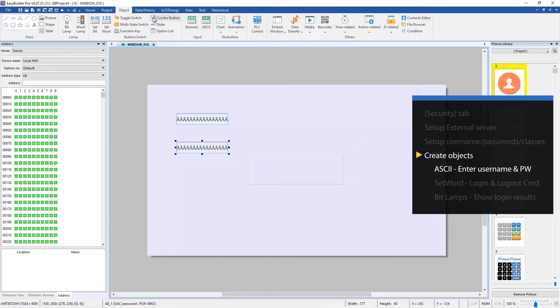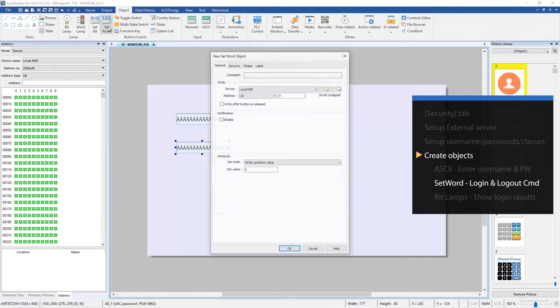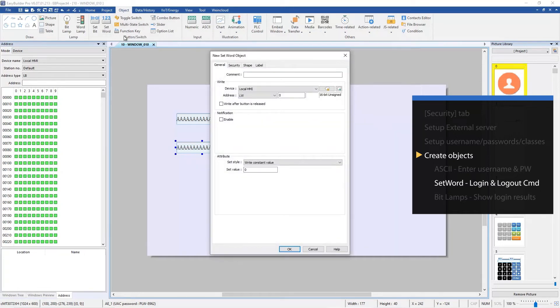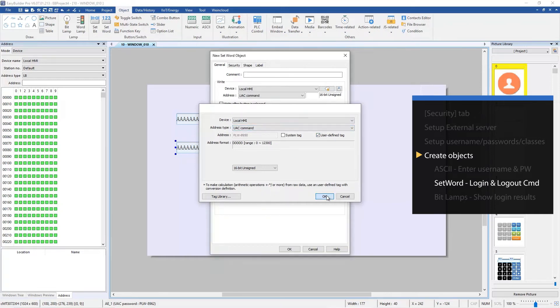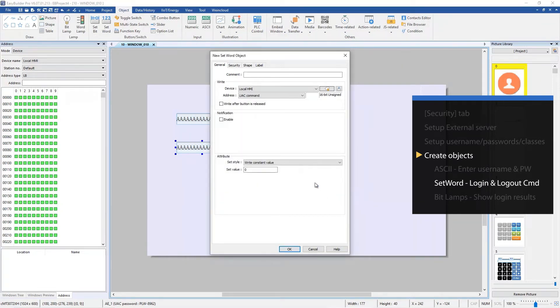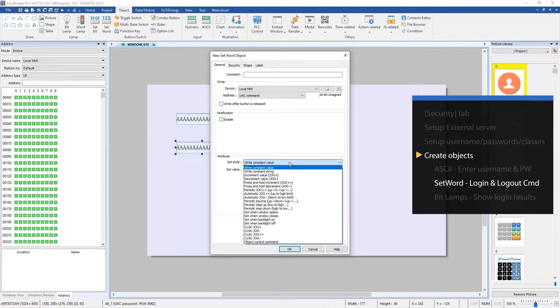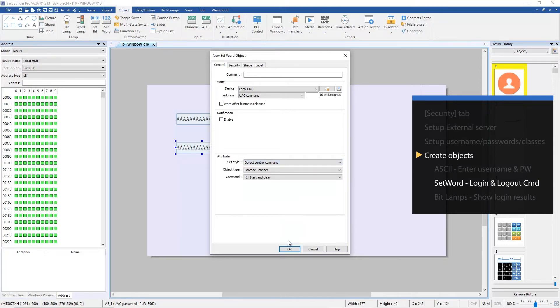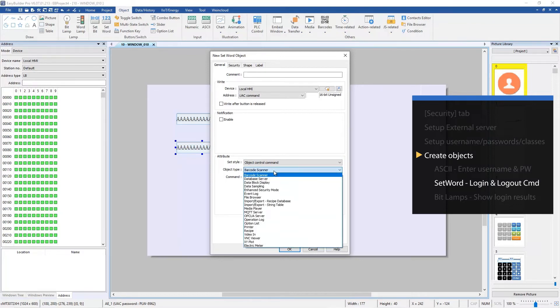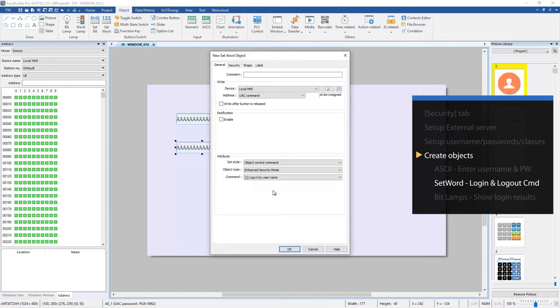Now let's create two set word objects for UAC login and logout. Click Settings, select UAC command as address type, select Object Control command as set style, select Enhanced Security Mode as object type, and select 1 Login by User Name.